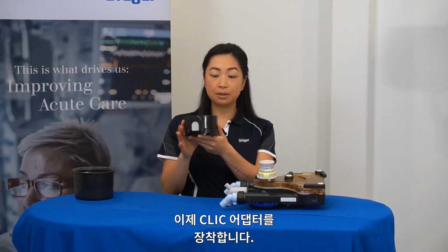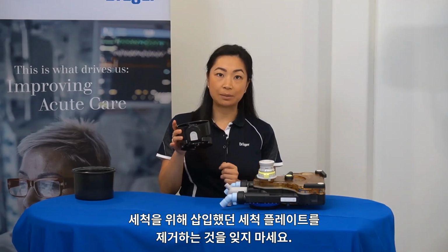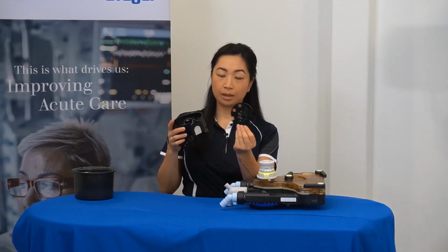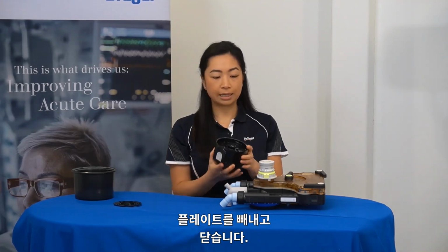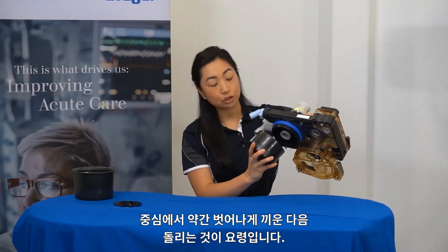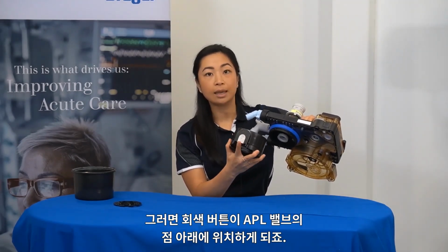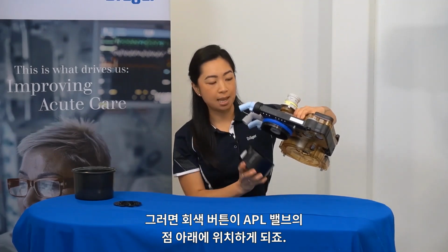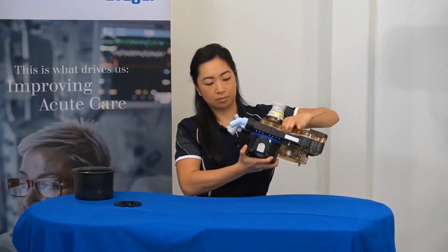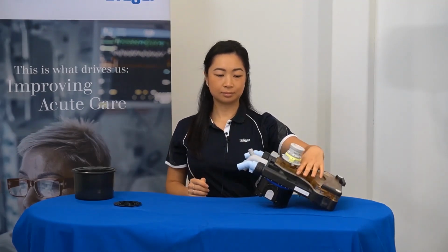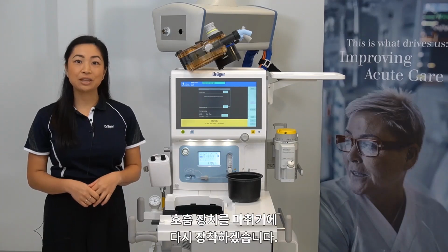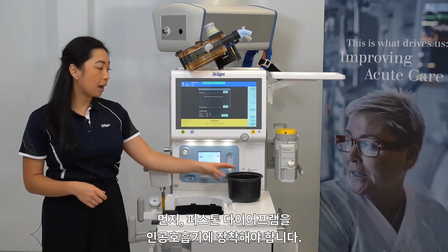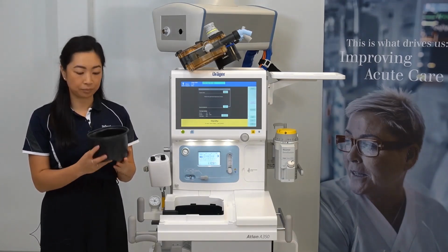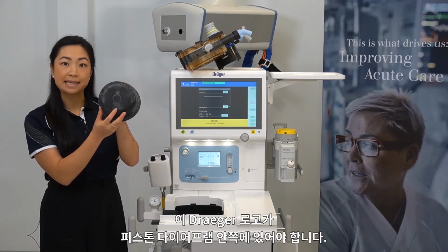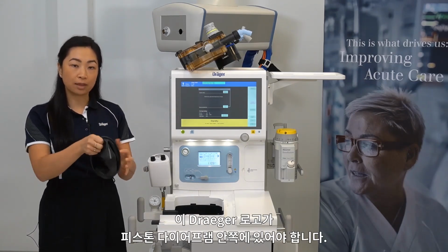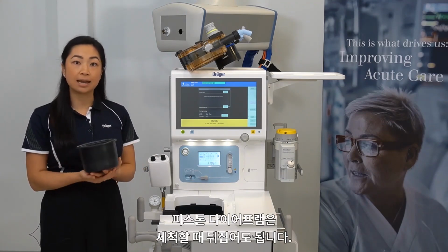Then take your CLIC adapter, but remembering to remove the cleaning plate that was inserted for cleaning. Sliding that out, clicking it shut. And the trick is to start off centre to land the grey button below the dots on the APL. To return the breathing system back to the device, start by returning the piston diaphragm to the ventilator. Just ensure that the Dräger logo seen here is on the inside of the diaphragm. This may have been turned inside out during the cleaning process.